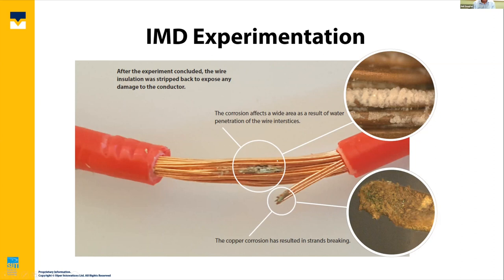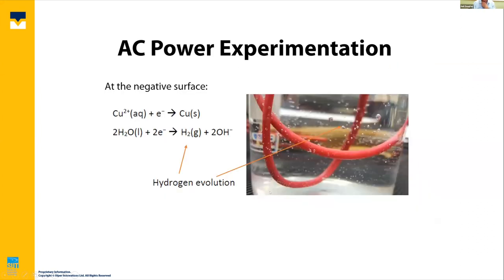So it's just verification that salt water is getting in. As a result of salt water getting in and us measuring the insulation resistance, we get some pretty horrendous copper corrosion. So then what we did was put two wires, the L1 and L2, into the same seawater container, and this time we applied just 220 volts. So our mains, we connected those two wires to the mains. And again, we damaged both wires. So both of them now have small holes in them.